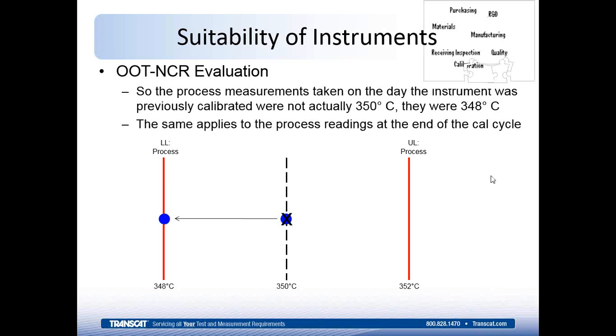All right, so the process measurements that were taken on the day the instrument was previously calibrated were not actually at 350. Now they were at 348 because that instrument had drifted all the way to the right. Now it's going to be adjusted back. And if you went back to take that measurement on that same process, remember the last day you did the instrument was under calibration just before it was turned in. You thought you were at 350. Now you're really at 348. So that process measurement is still good, but it's right on the limit.